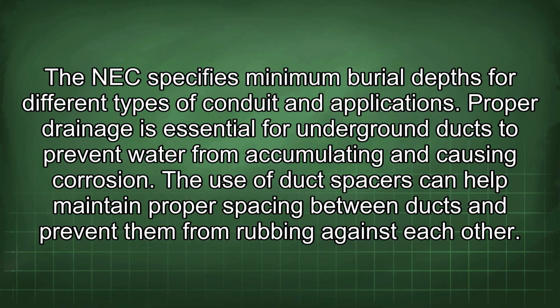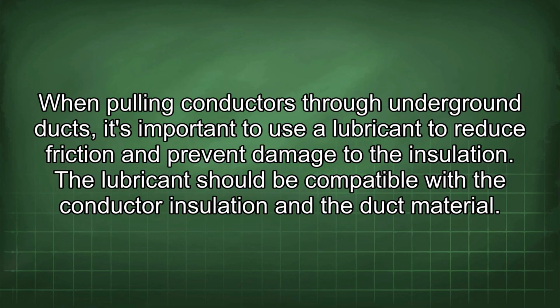The use of duct spacers can help maintain proper spacing between ducts and prevent them from rubbing against each other. When pulling conductors through underground ducts, it's important to use a lubricant to reduce friction and prevent damage to the insulation. The lubricant should be compatible with the conductor insulation and the duct material.